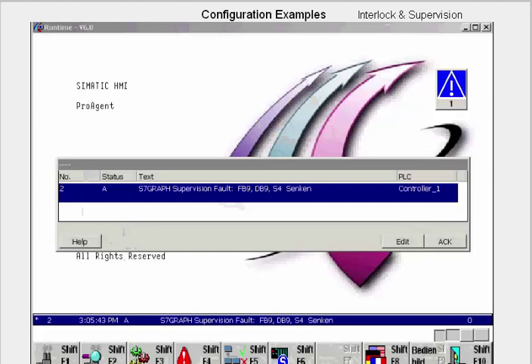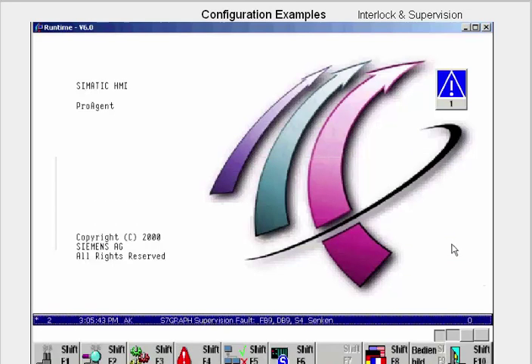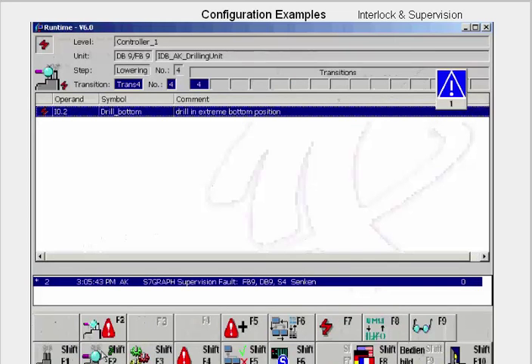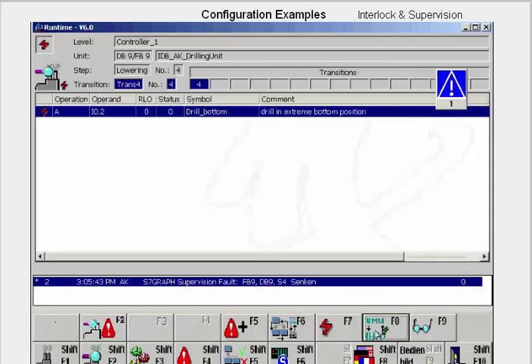Once a process fault has been triggered for which the supervision has been configured — in other words, the lower step was not completed within the time limit set — the supervision fault is announced in a message window. We acknowledge the message and switch to the overview, in which we can see at which level and in which unit the fault has occurred. In the detailed picture, you also get a display of the step, the transition, and the faulty address. With the F8 button, we switch over to see with which operation this address is linked.